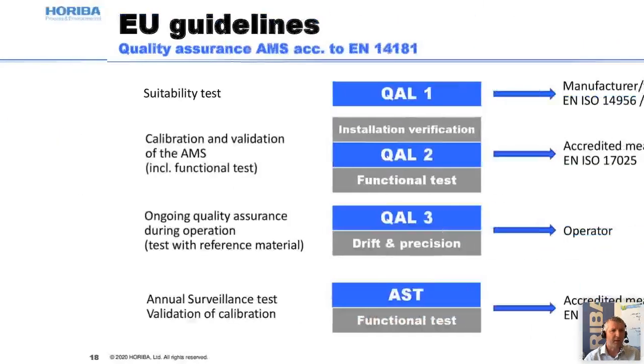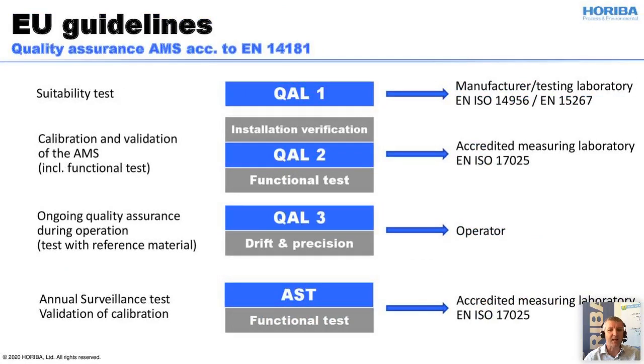the data acquisition system. As a summary, I have added this slide right here, and we start with the suitability test, which needs to be done by the manufacturer and the testing laboratory. This is the QAL1. After the installation, it needs to be verified with the QAL2 step. This again needs to be done by a measuring laboratory, which is certified to ISO standard. After that, on a frequent level, we have the QAL3 procedure, which the operator and the plant owner are responsible for. And not to forget the annual surveillance test, the validation of calibration with the accredited measuring laboratory again.